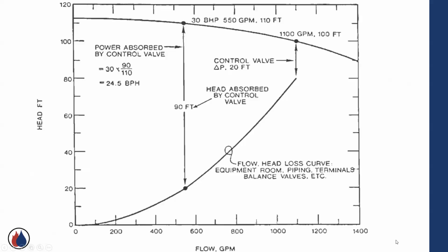And this is, again, an older chart, showing a pump curve. As a quick example, here are my design conditions. I need 1,100 gallons a minute at 100 feet of head loss for this big campus distribution system, whatever it is, big apartment complex, big hospital. When all the valves are open and everything's calling, everything's fine. And I might have a control valve pressure drop of 20 feet. That's a little bit about what we just discussed on sizing control valves with a Cv, trying to create some control valve authority. I want a valve that can control at each terminal unit. Whether I have 50 or 100 or 20 terminal units, I'll have a control valve head loss. And so when everything's open and running, I'm at my full design flow of, say, 1,100 gallons a minute.